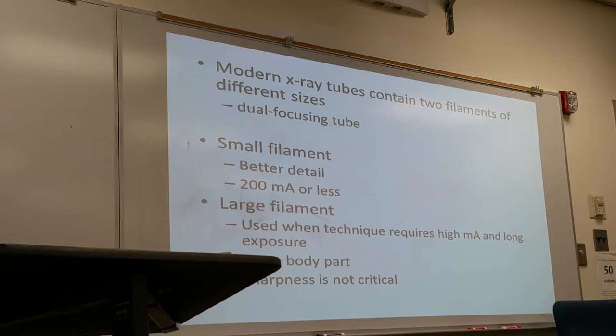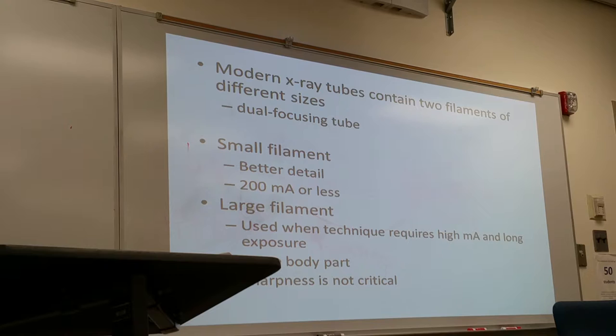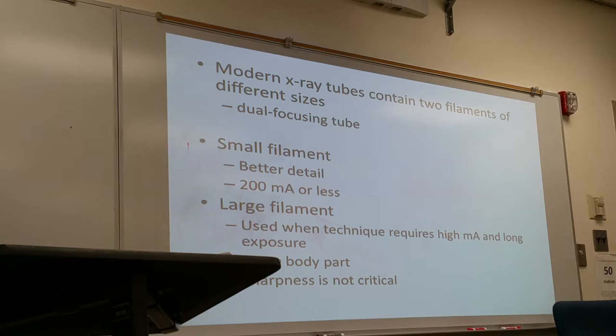In today's x-ray tubes, there are usually two different sized filaments — one large and one small — in what's called a dual focusing tube. The reason is mainly for different body parts and for resolution. The smaller filament generally gives you more detail because the beam is much more concentrated. However, with the smaller filament, you can only use certain mA settings — generally 200 mA or less. Anything more would cause excessive wear and tear on the smaller filament.